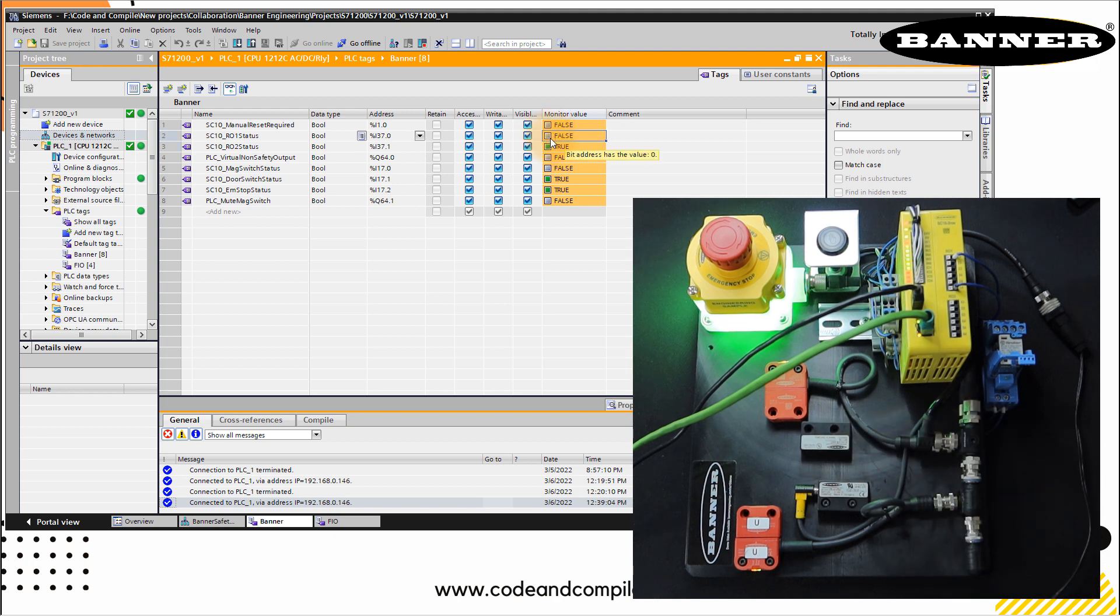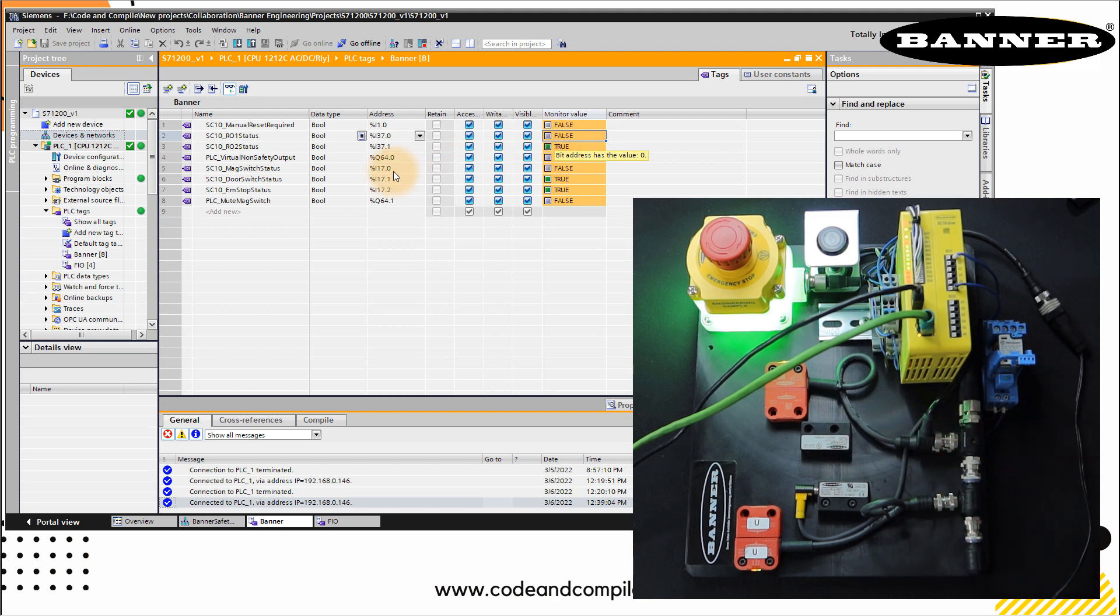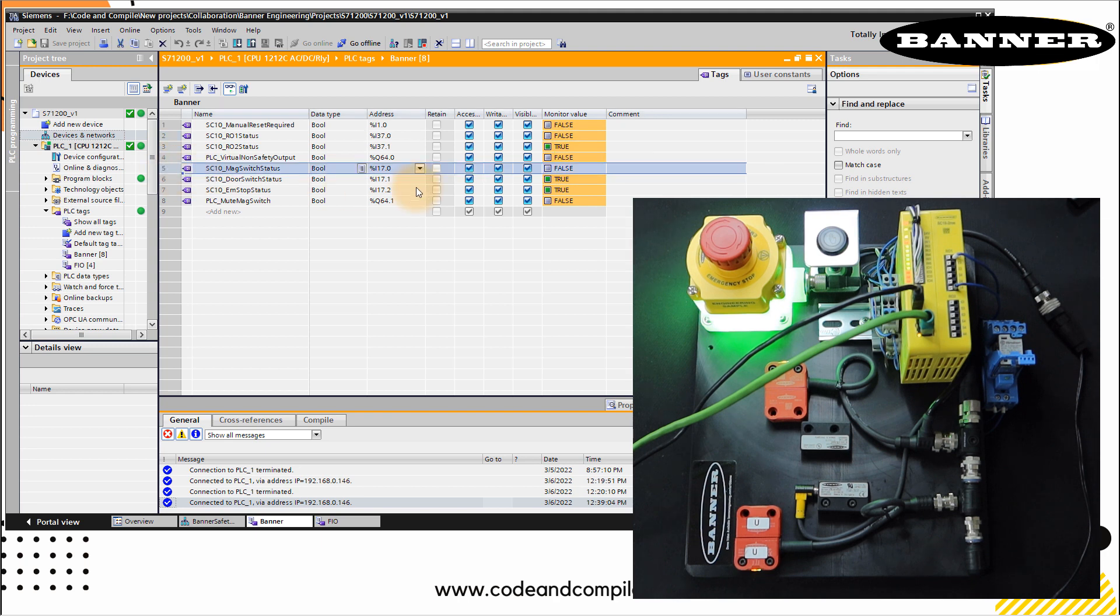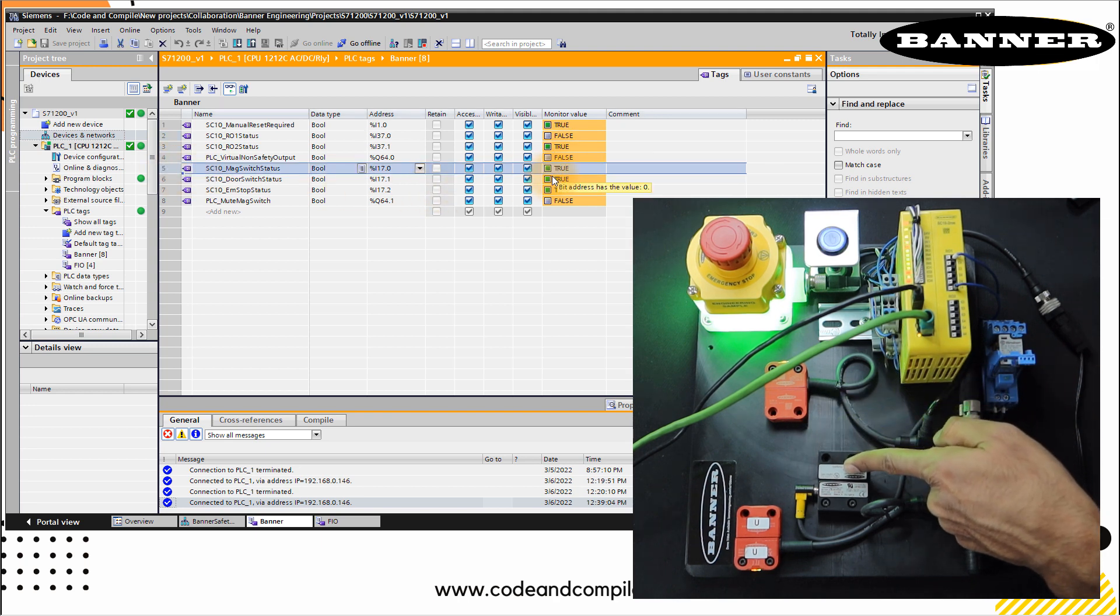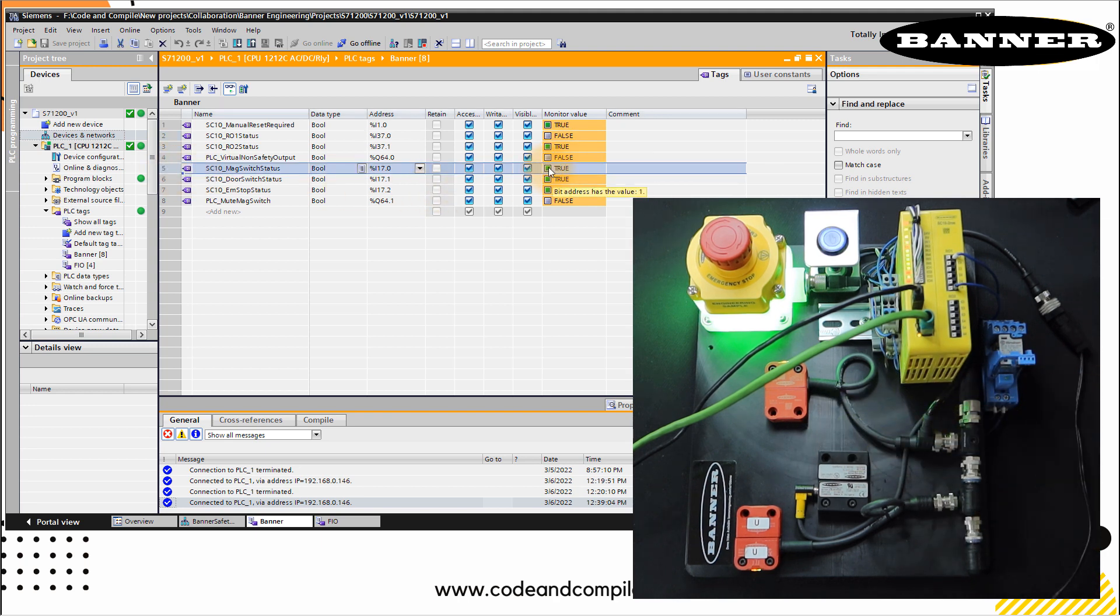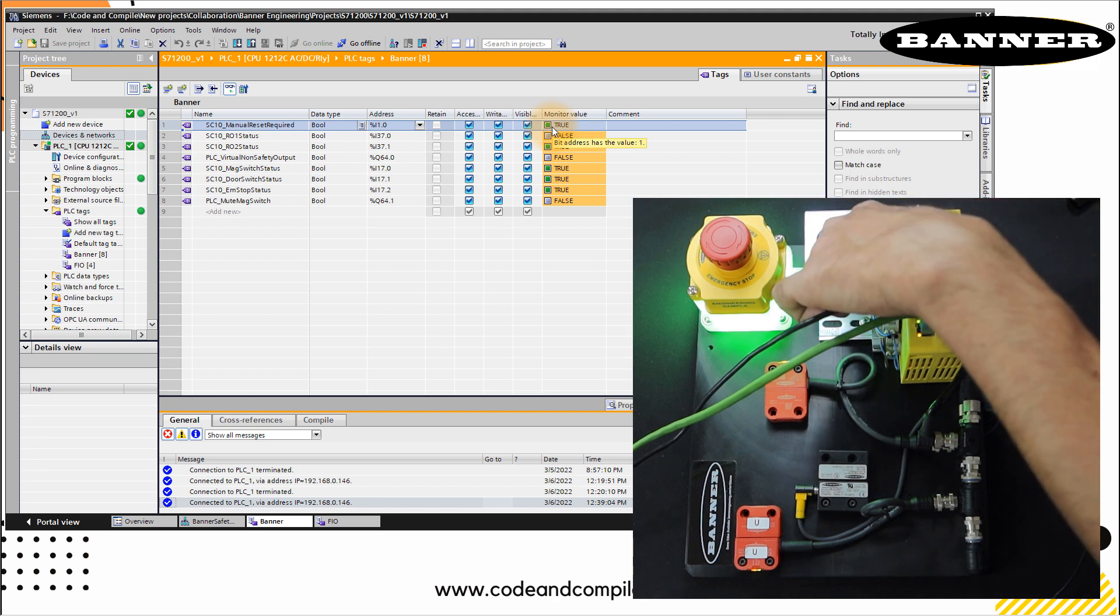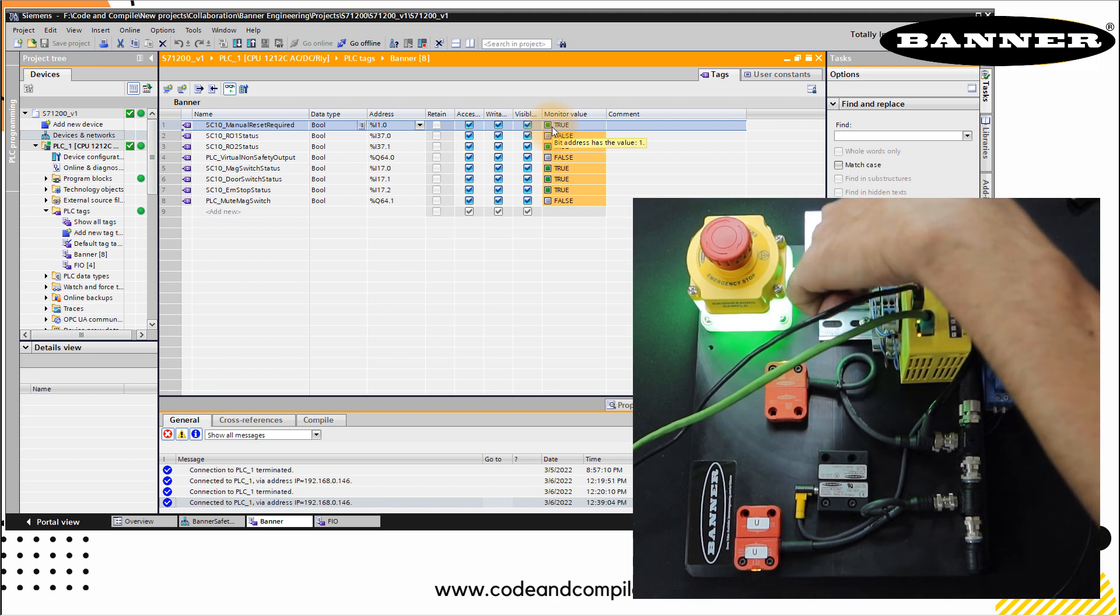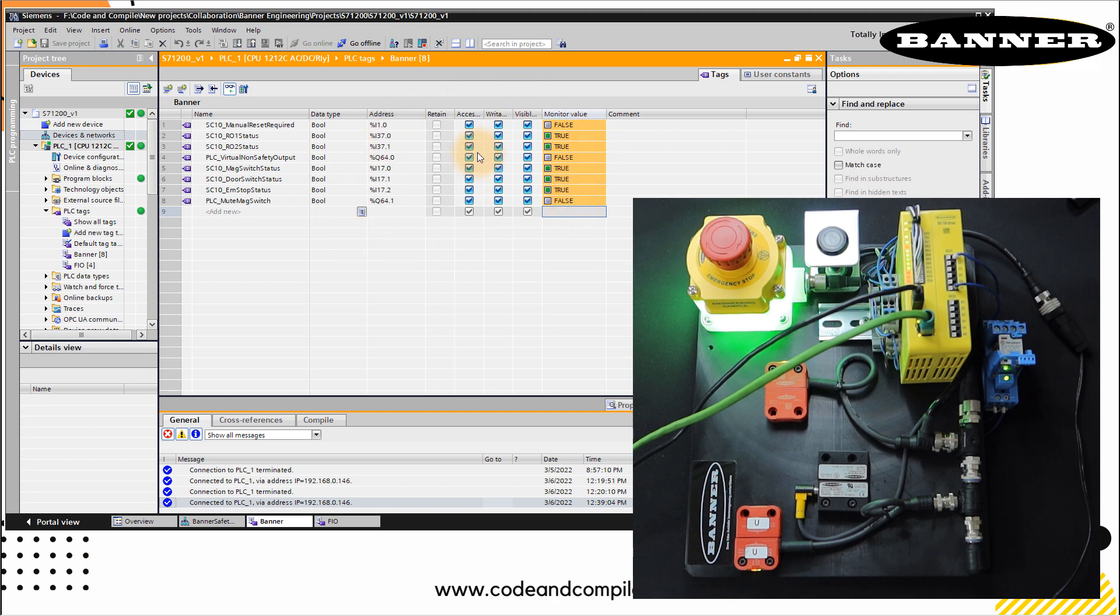This I'm reading by PROFINET from the SC10 control. Once I bring back the sensor, you can also see this magnetic switch is false. Once I bring this back, you can see this is true. You can see that here reset required is also true. So all I have to do is just go and press reset. And it will reset the circuit. This is very interesting. Very easily you can read the information of your safety controller in your PLC.